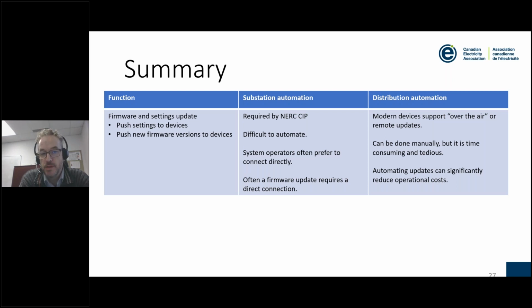Also, system operators, especially for firmware deployment, will often prefer to connect directly and locally. Even if they have remote access to devices, those devices, especially protection relays, are too critical to the network to be updated remotely, so they still prefer to do that on a direct connection. Besides, a lot of those devices actually force you to perform the update directly using a local port in front of the device, and you cannot do it remotely.